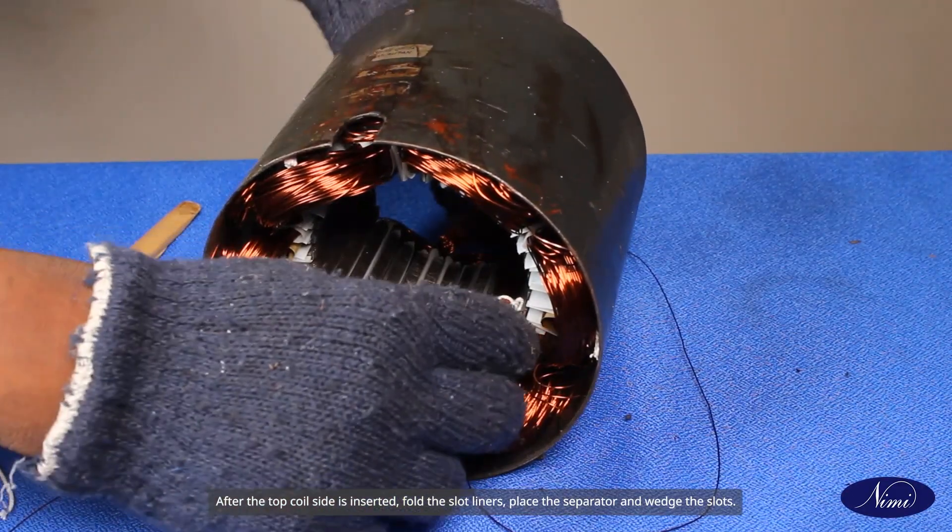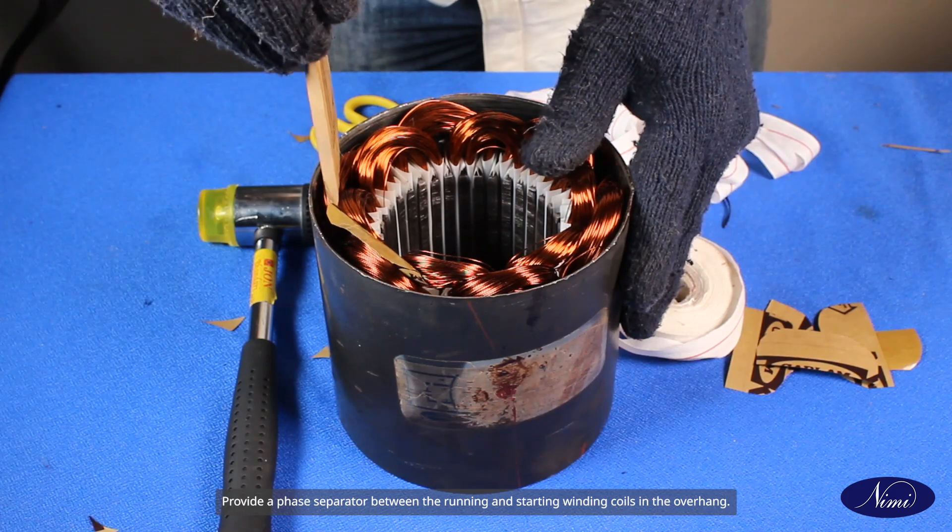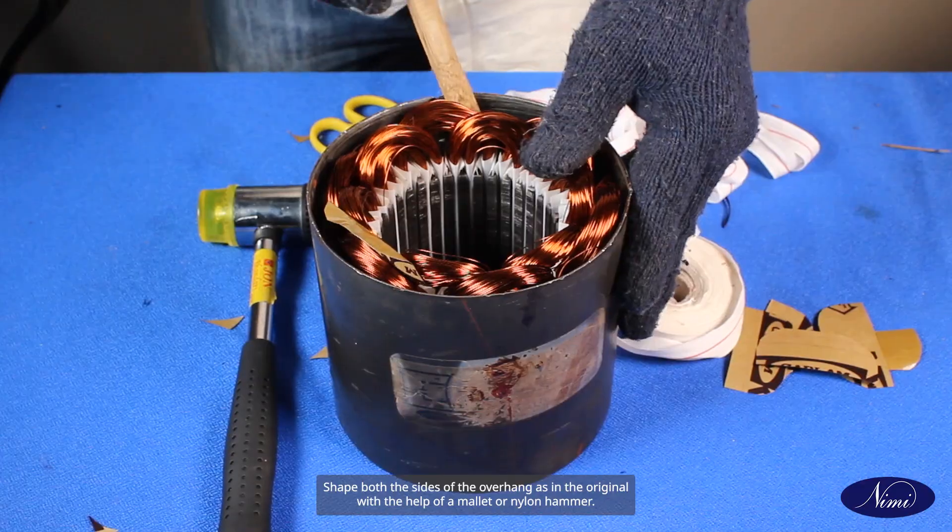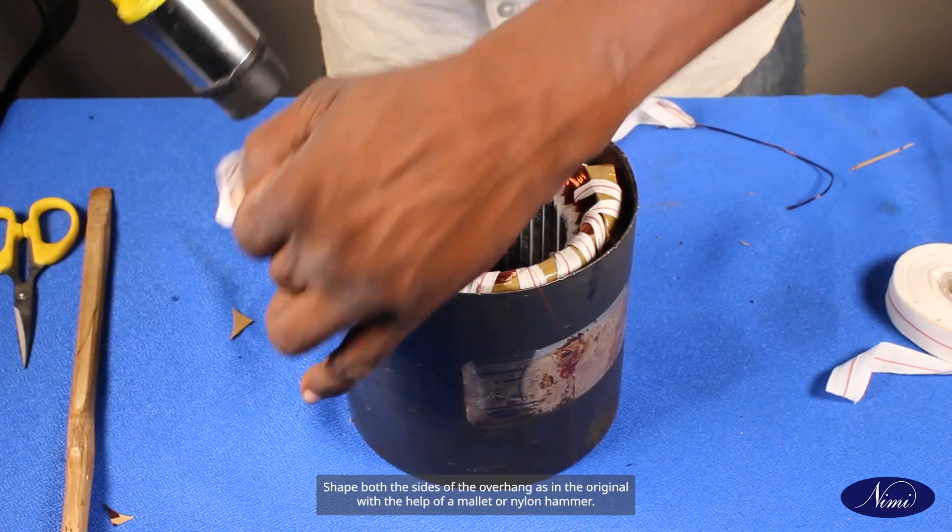Place the separator and wedge the slots. Provide a phase separator between the running and starting winding coils in the overhang. Shape both of the sides of the overhang as in the original with the help of a mallet or nylon hammer. Apply uniform mild blows, avoid damage to the wires or insulation.